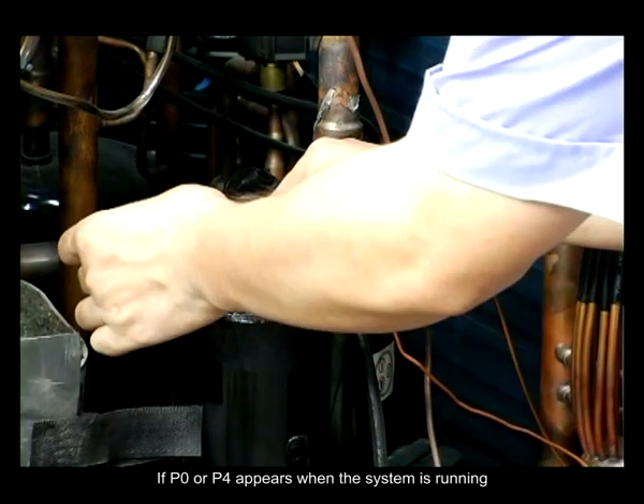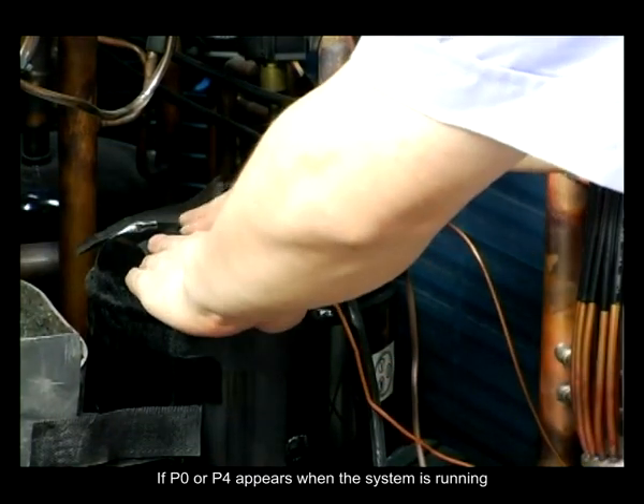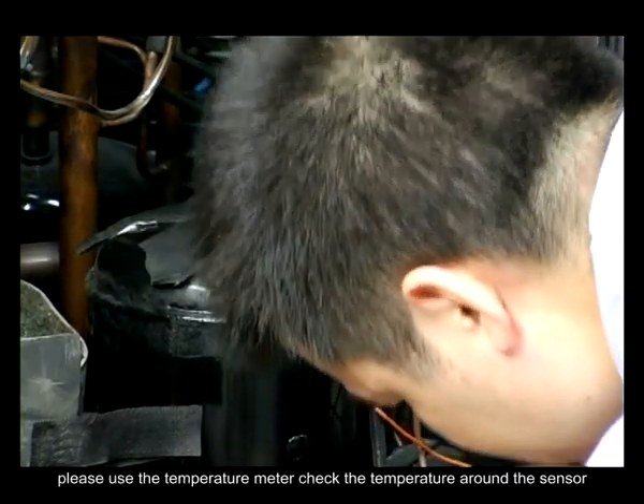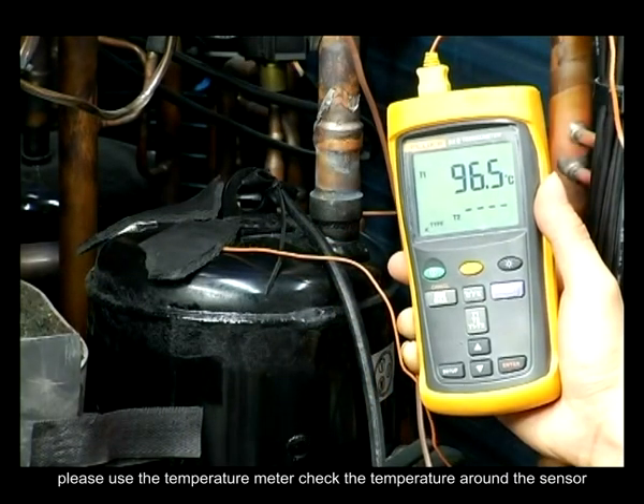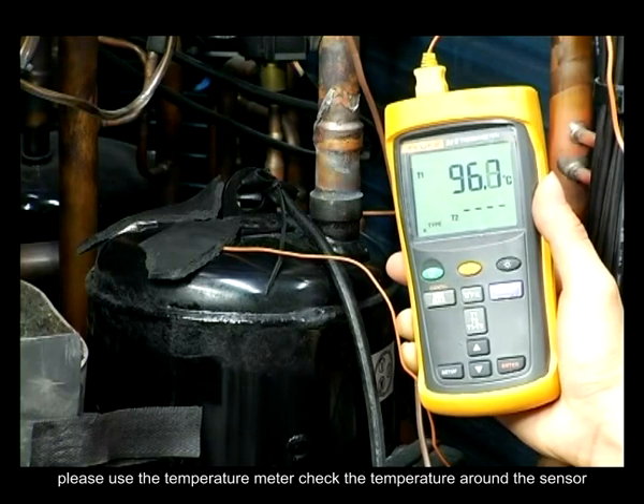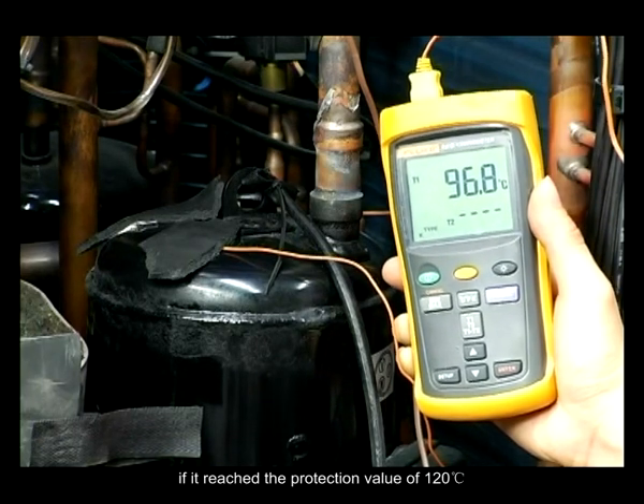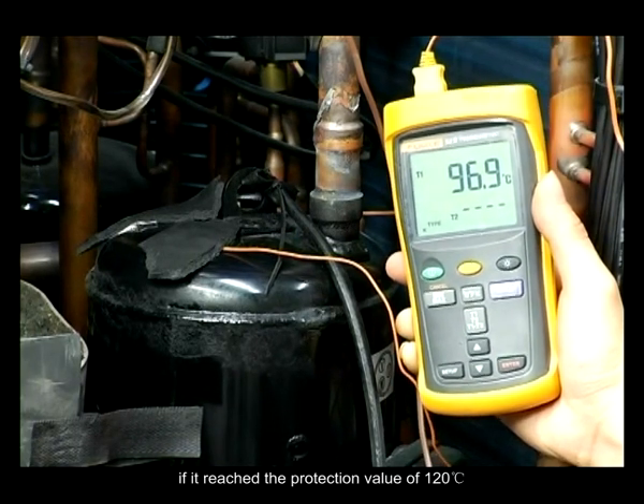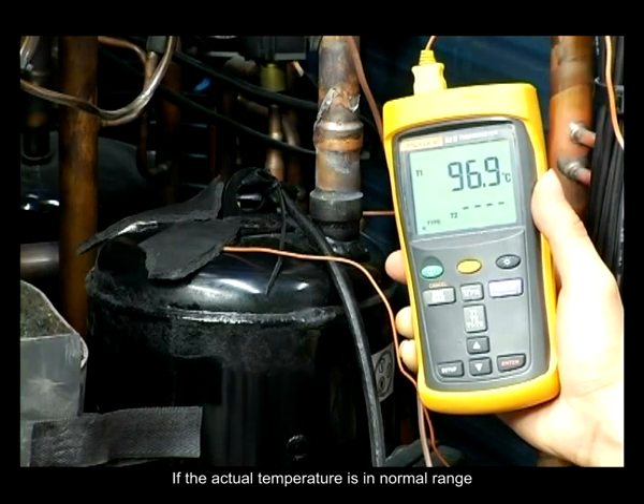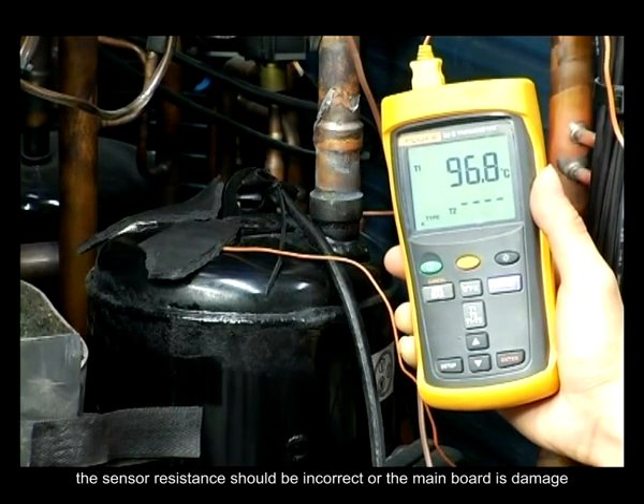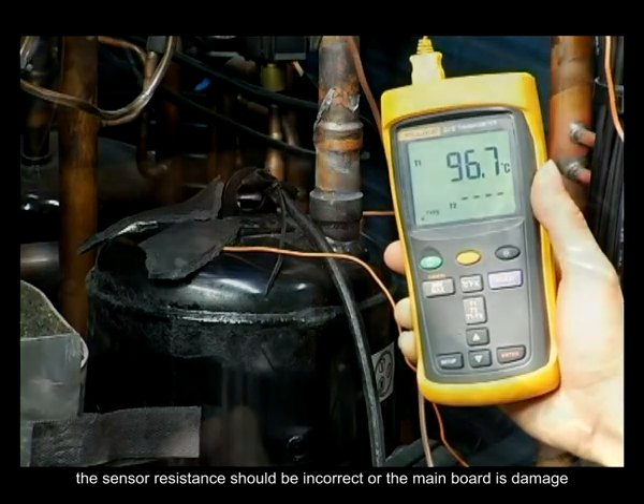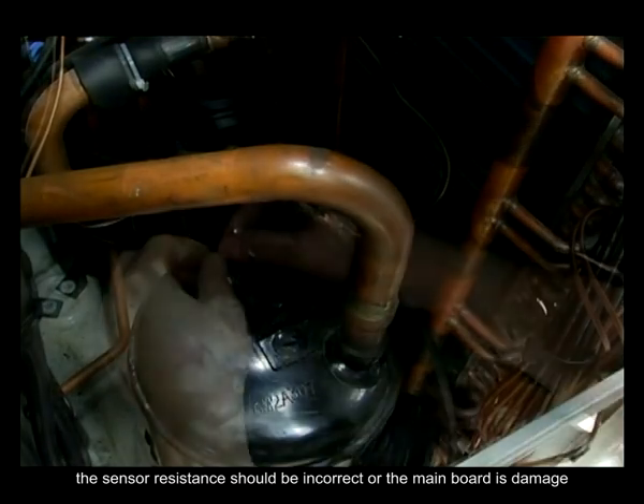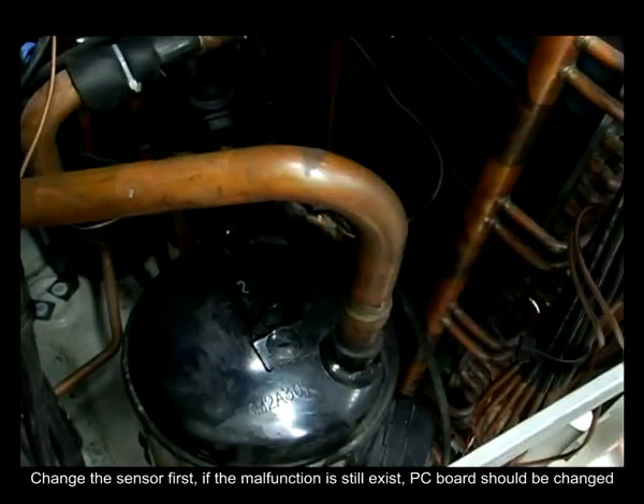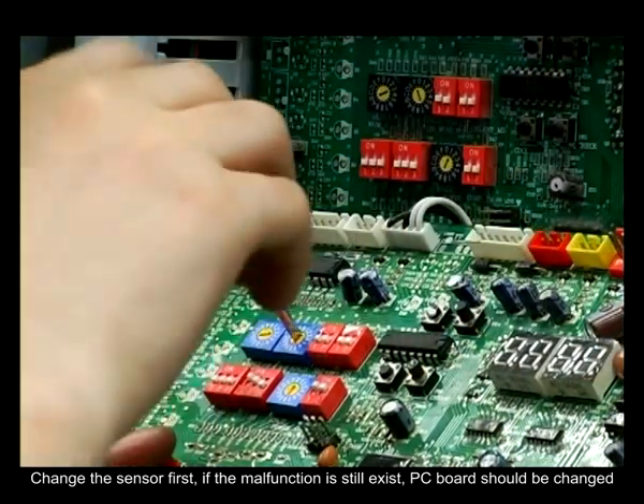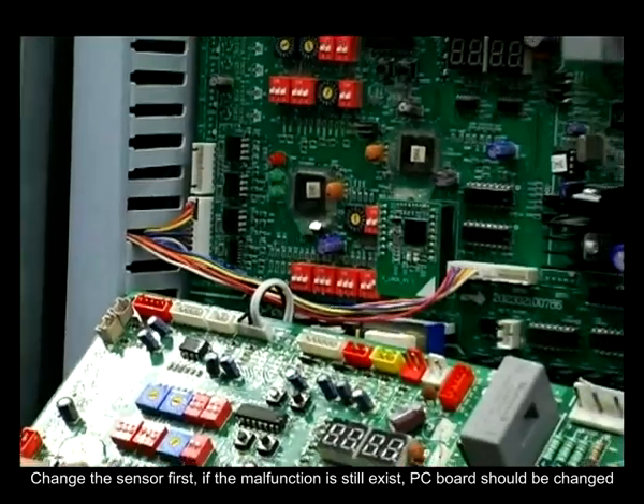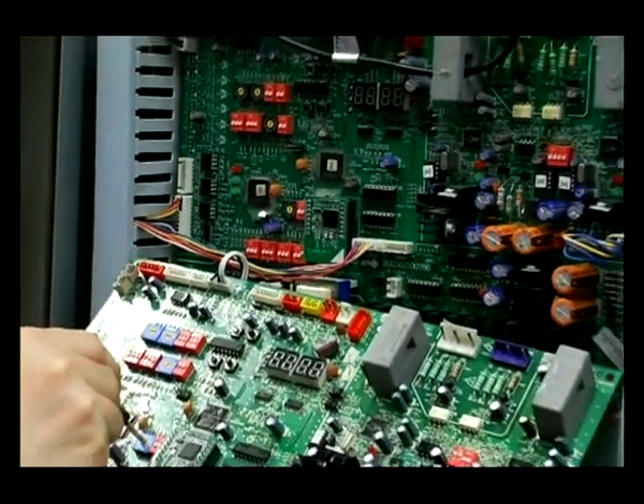If P0 or P4 appears when the system is running, please use the temperature meter. Check the temperature around the sensor. If it reached the protection value of 120 degrees Celsius. If the actual temperature is in normal range, the sensor resistance should be incorrect, or the main board is damaged. Check the sensor first. If the malfunction still exists, PC board should be changed.